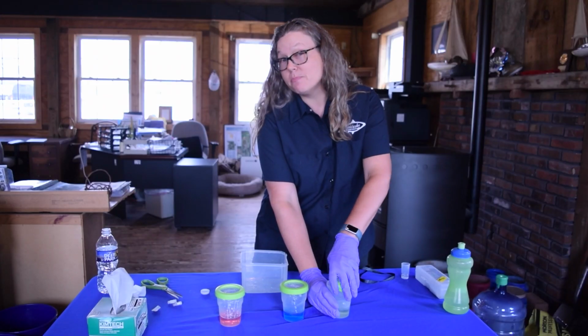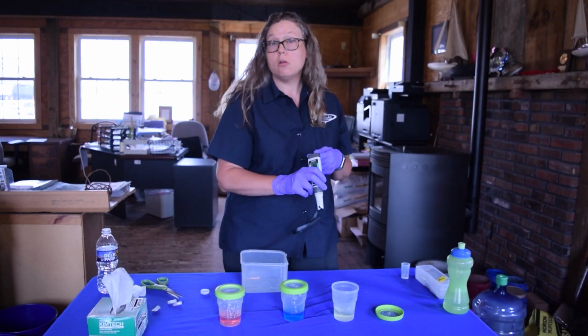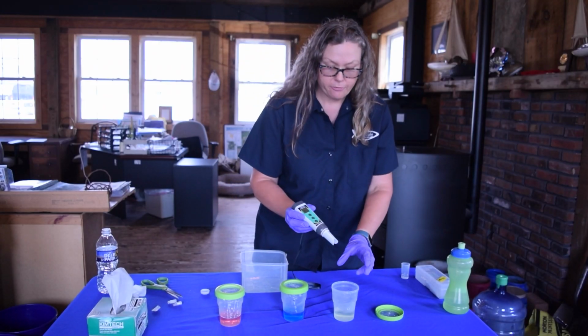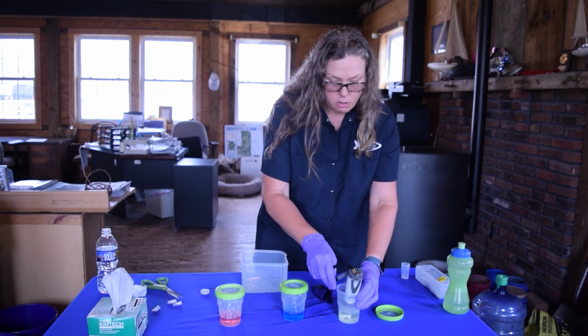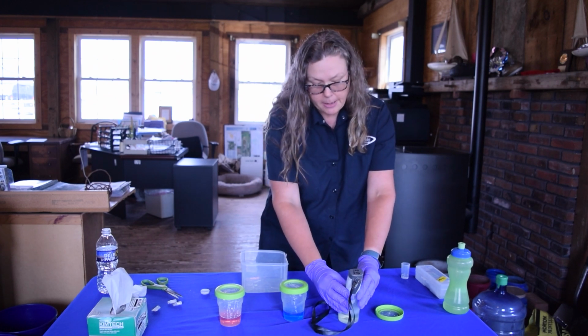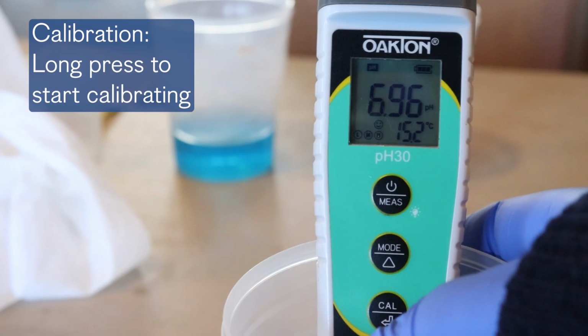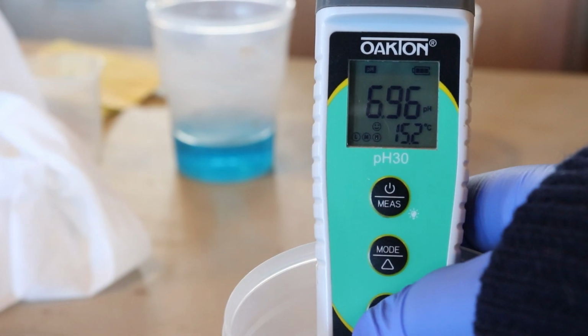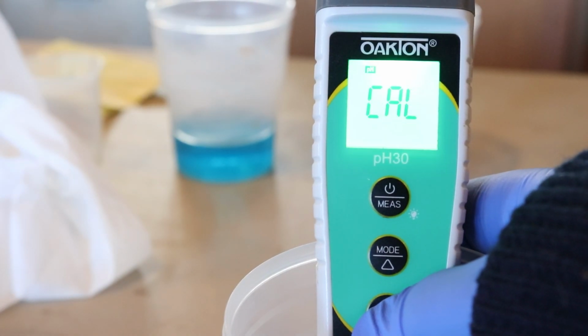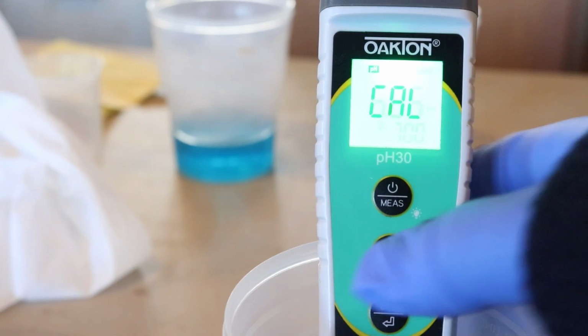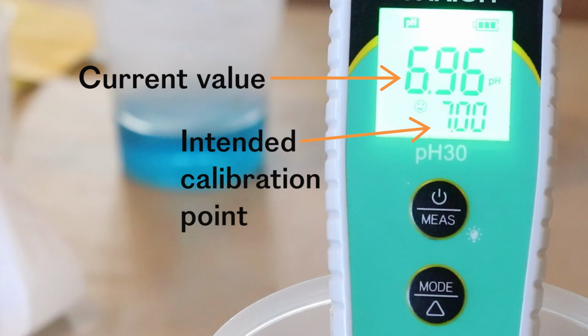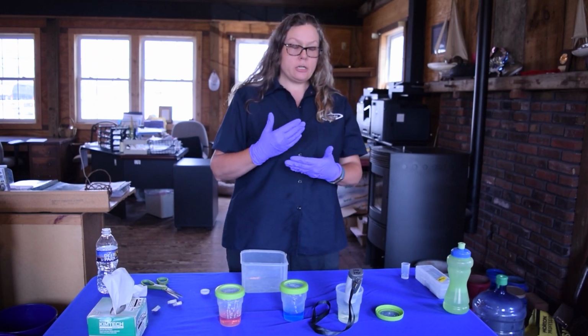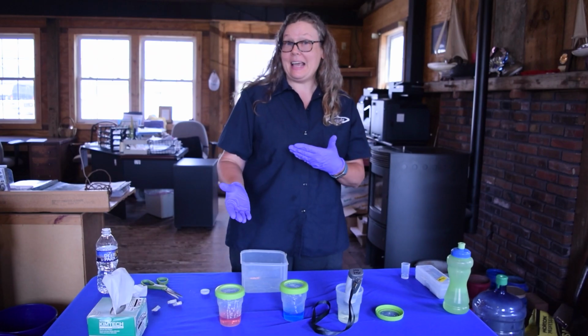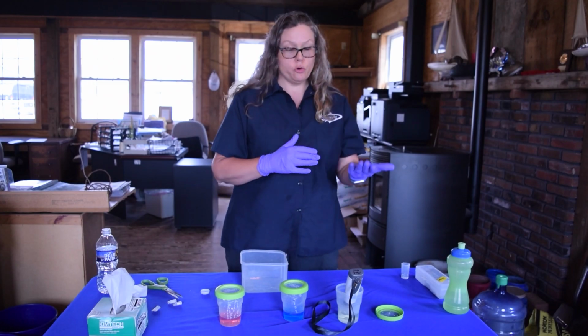And we always must start with the neutral or 7 buffer. I like to give it a stir, insert the pH meter, and then we're going to do a long press on the cal button. You'll see cal pop up on the screen. You'll see the current pH value along with the intended calibration point. So the meter is going to automatically detect which buffer solution you are using.